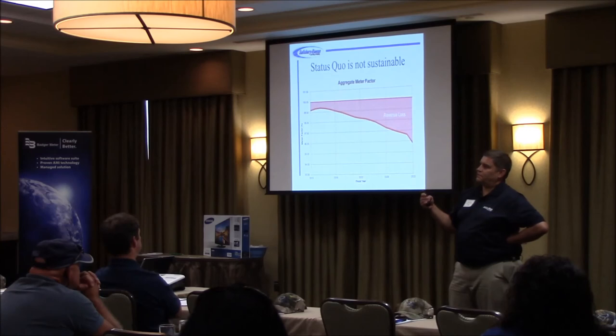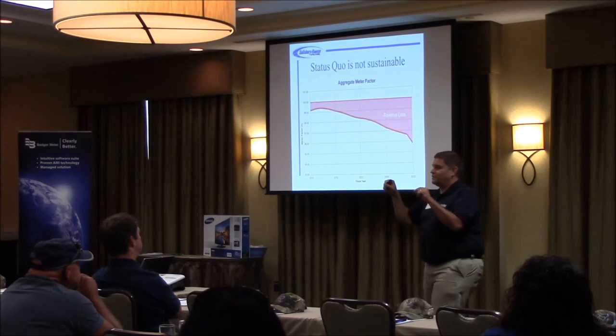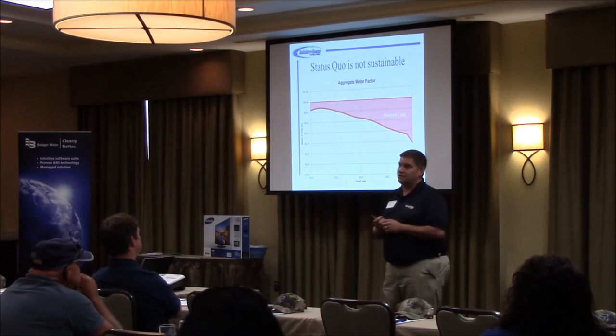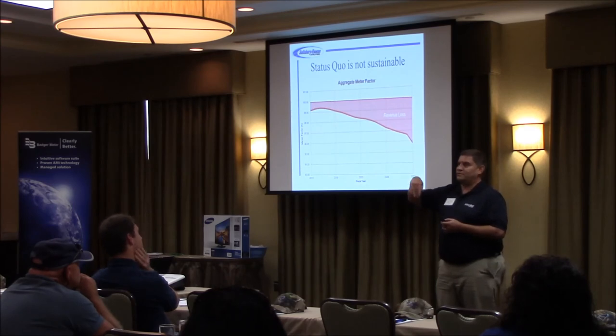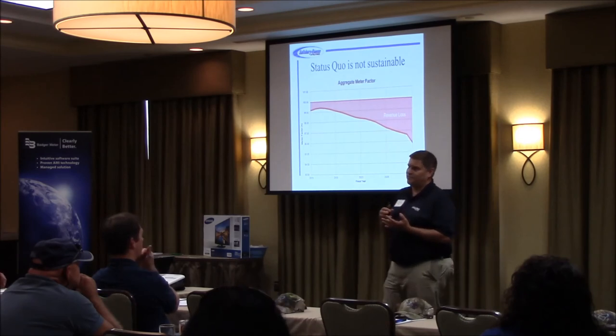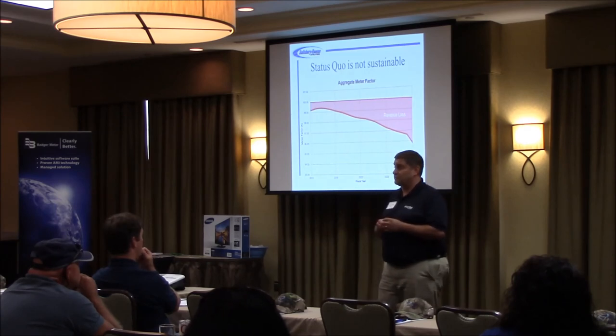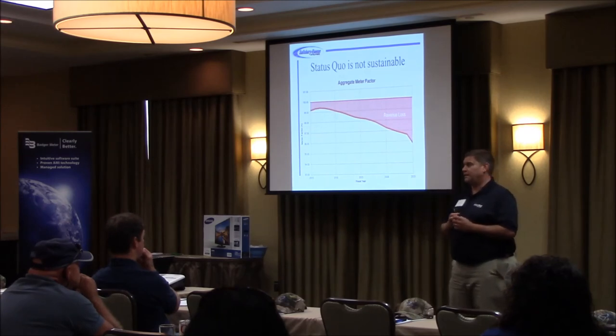With that Utah State study, we're looking at the water going through one meter and then through the other, and they're measuring exactly the same amount of water. What happens over time with that mechanical meter, how quickly does it drop off? The customers that are in there, we've got a cross section, even though it's five houses on one side of the street and five houses on the other side. We've got one vacant house right now. We've got some that are using about 200 gallons a week, and some that are using 1,500 gallons a week. So it gives us a cross section of those residential customers.